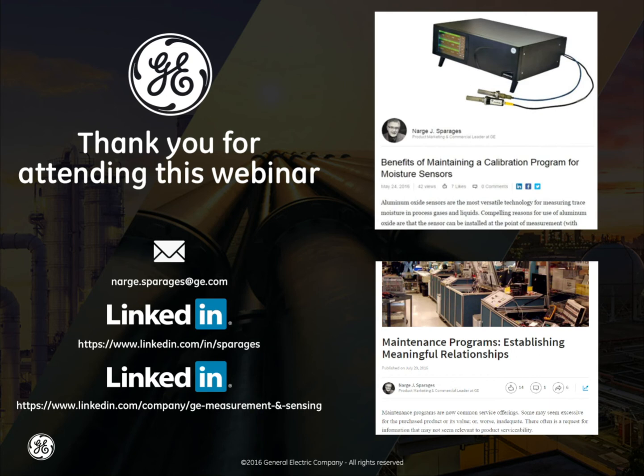Therefore, for ultra-high purity applications, whether they be for semiconductor applications or, for that matter, applications where the sensor's after an emulsive dryer and the accuracy is of great importance, that it's not just there to trend and to alarm on rate of rise, we have what's called a low-end calibration system. In this case, we're exposing the sensor to ultra-dry moisture levels for weeks before we start generating any moisture contents. The whole calibration system is in a different state than it would have been had we been purging it only for a week. So the whole system is in a different state, and then we generate frost points as low as minus 100, minus 90, minus 80, and we wait for equilibrium to occur at each of those points. That's a very specialized calibration for a very specialized application.